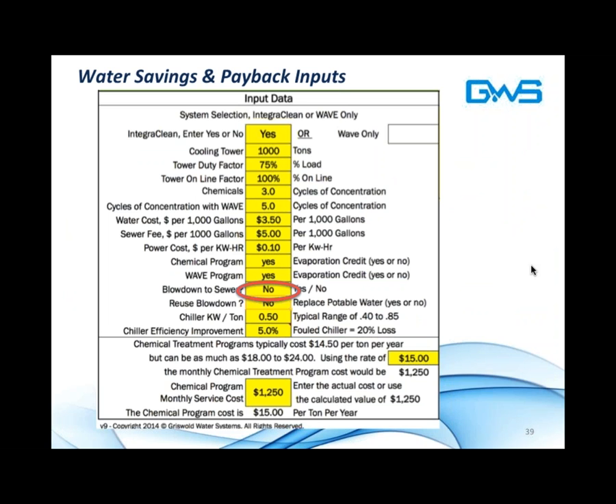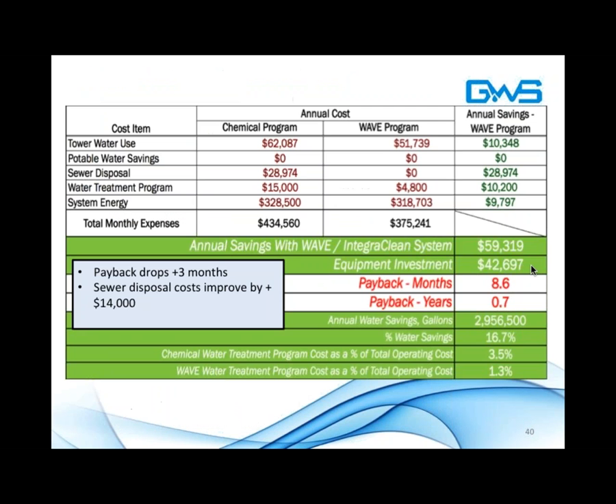One final case here before we end this, and that is to reuse that blowdown water. Why? Because it's chemical-free. It's not saturated with toxic biocides. And in every municipality that we've researched, the authorities will allow that discharge, that blowdown, to go over the side of the building, which means that the customer no longer has to pay the sewer discharge fees. And when that happens, payback improves even greater.